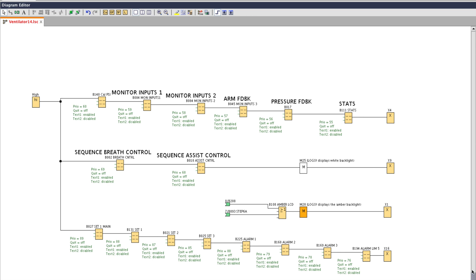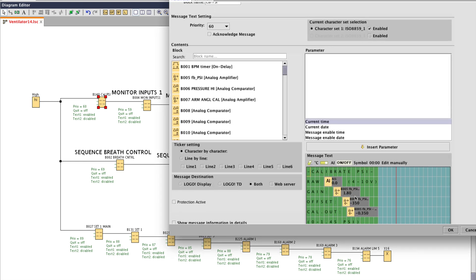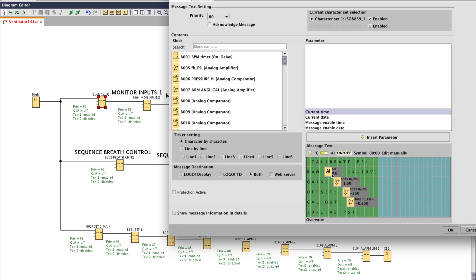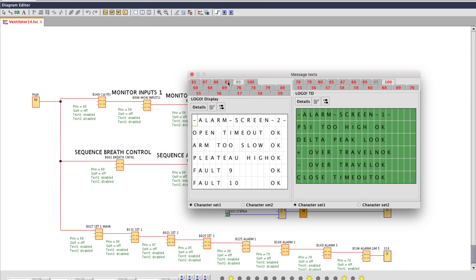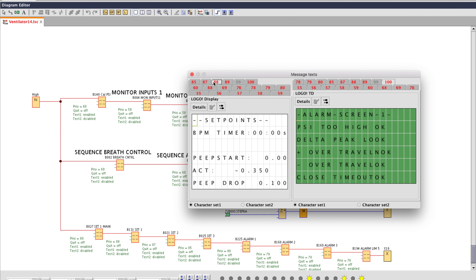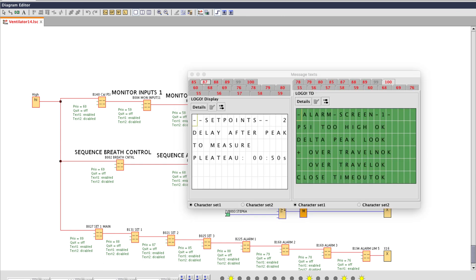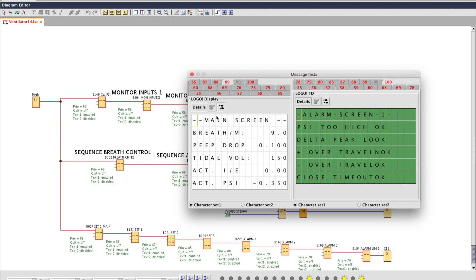Scrolling down to the last page now these are the majority of the message instructions that I have in the PLC. So these are all the screens that you scroll through when the machine is running. And just like the alarm screens you can configure what's displayed. Here I'm displaying an analog input value. On the other lines I'm displaying things like gain or inputs to a math instruction. We can click a button to simulate the PLC running on our computer. And we can scroll through all the screens to see what they look like. And you'll see the traces in the program in the background turn red if they're true. And my screen capture got cut off a little bit on the bottom but you can type in values for all the analog inputs. You can flip toggle switches for simulating the inputs. The light bulbs across the bottom are showing you the value of some of the boolean memory addresses. You can also connect to the PLC using Ethernet and see all the values live for troubleshooting.